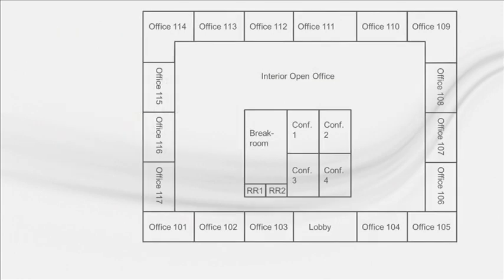Let's look at an example office building that will use a VRF system. This building is too large for a single VRF system to handle it, so we'll need to divide the building into zones that match outdoor unit capacity. If we zone this building to use heat pump VRF systems, the zones connected to the outdoor unit must have common heating and cooling needs. If not, the zones that require cooling will be uncomfortable during the time the outdoor unit is attempting to satisfy the zones that require heating and vice versa. So it's necessary to break up the building into zones of similar daily and annual load profiles. Offices 110 through 113 on the north wall of the building are likely the same load throughout the day and year, so they would be potential candidates for a single heat pump system.